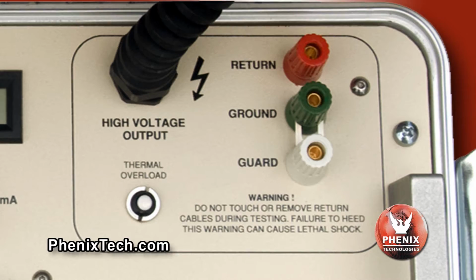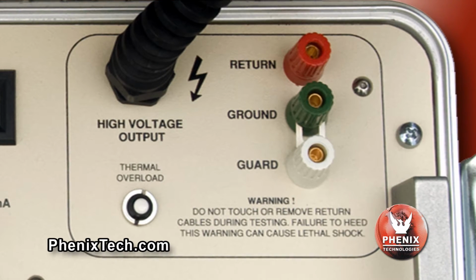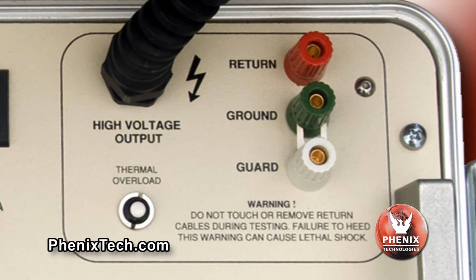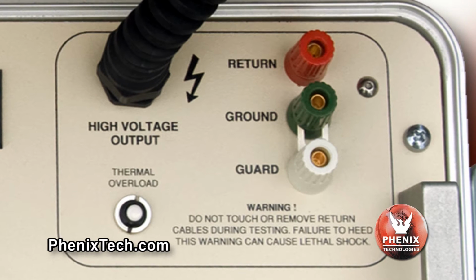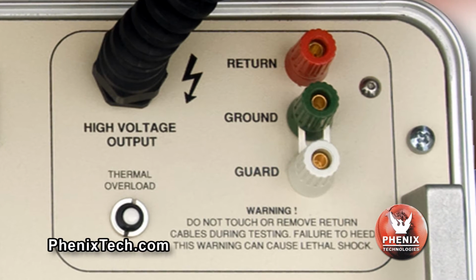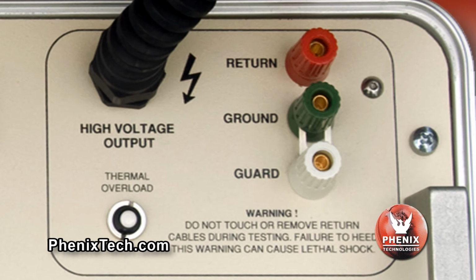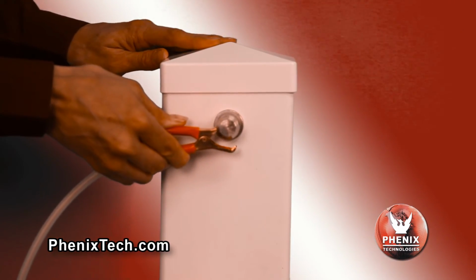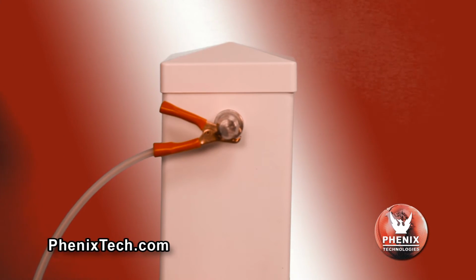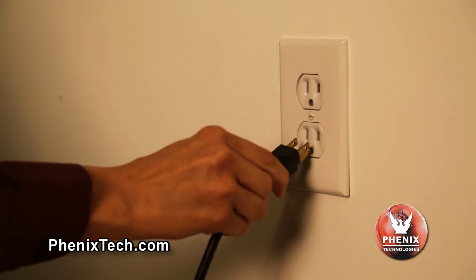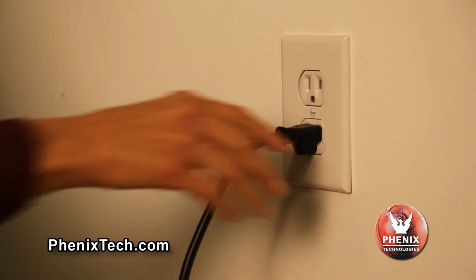For test objects that have the low potential side isolated from ground, there is an alternative connection, as shown with model 475-20, with the slip clip between the ground terminal and guard terminal that will allow the current meter to read only current passing through the test object. Do not operate unit with the slip clip removed or not connected to either return or guard terminal. Connect the high voltage output cable to the high potential side of the test specimen. Connect the input main power cable to an appropriate power source.